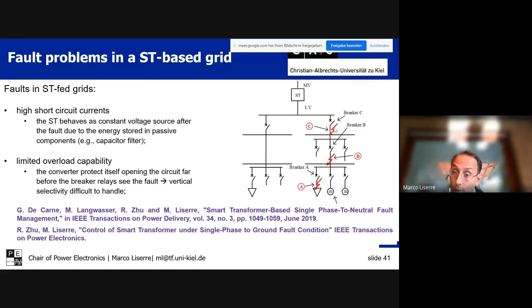We have published work, and also recently been awarded a patent, on what happens when you have a fault and lose one phase. With a smart transformer, you can continue operating the system on 2 phases, and then you have to decide whether to shift by 90 degrees or 180 degrees.